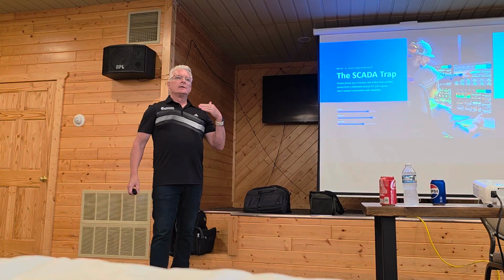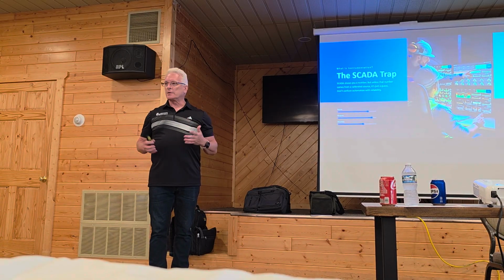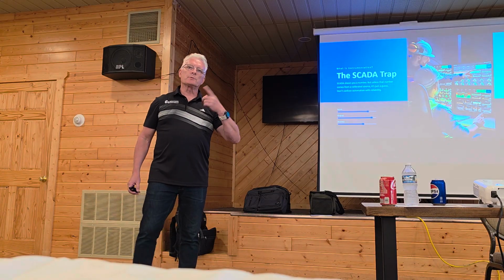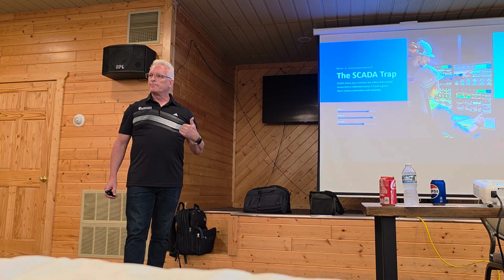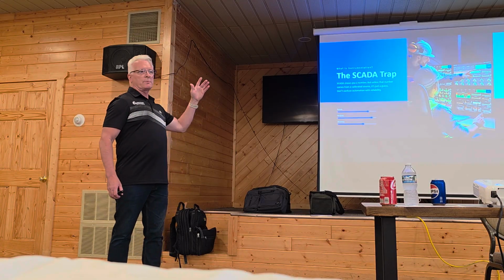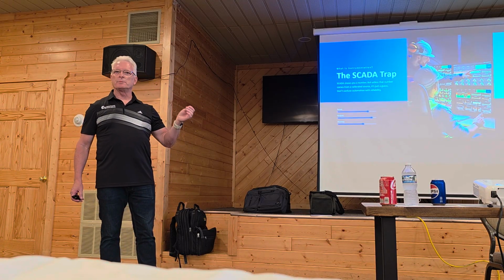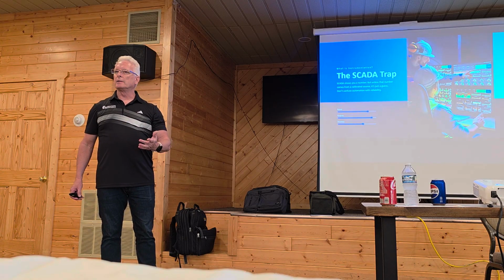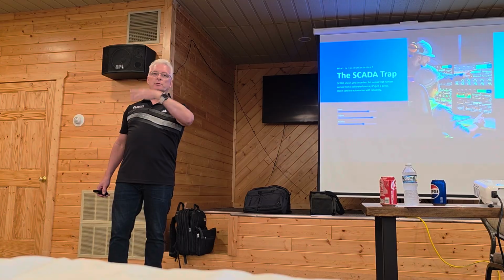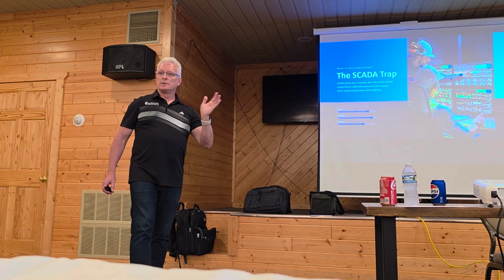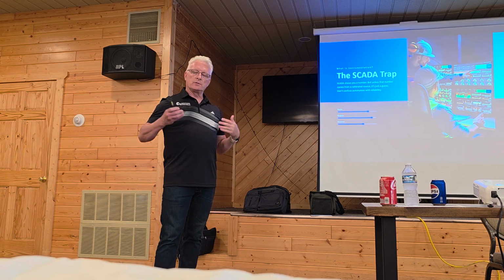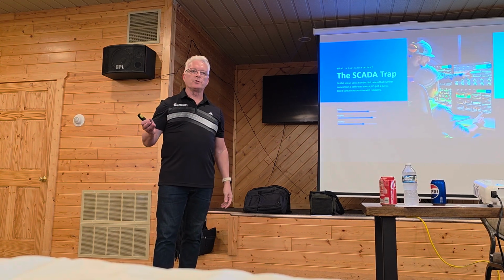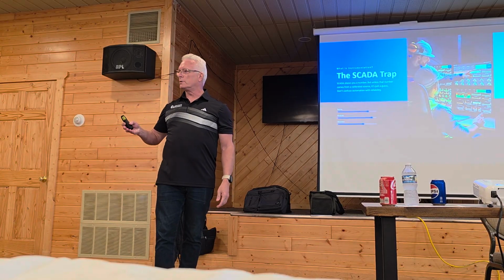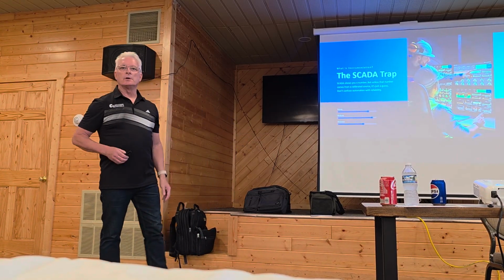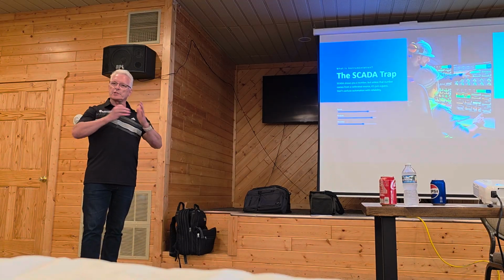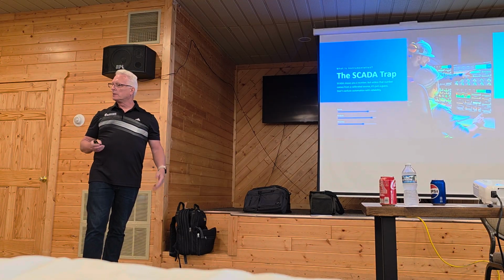One of them is we try to check the host system as well as we can, because sometimes the documentation isn't there. But we try to test the host system as much as we can. We do that by simulating with our equipment, find out what the system's supposed to be doing, and then we work backwards to make sure that that device, that instrument was set up correctly for 0 and span, and that correct information is now being sent, whether it's through a radio, PLC, whatever it is. So we make sure that whole system is correct as well as we can, and we document it so that if something happens in the future, we've got the information to replace it or troubleshoot it or get it back up to where it was before. So then after that, we don't do that unless you see a problem. But the first time we try to go through the whole thing, document it, and make sure it's correct.